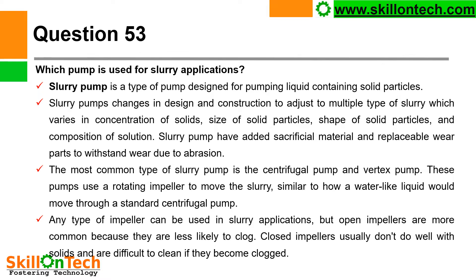Closed impellers usually don't do well with solids and are difficult to clean if they become clogged. Therefore, during clean water applications we use closed impellers; in case of pure slurry we use open impellers; and in case of slightly muddy water we may use a semi-open or semi-closed impeller.